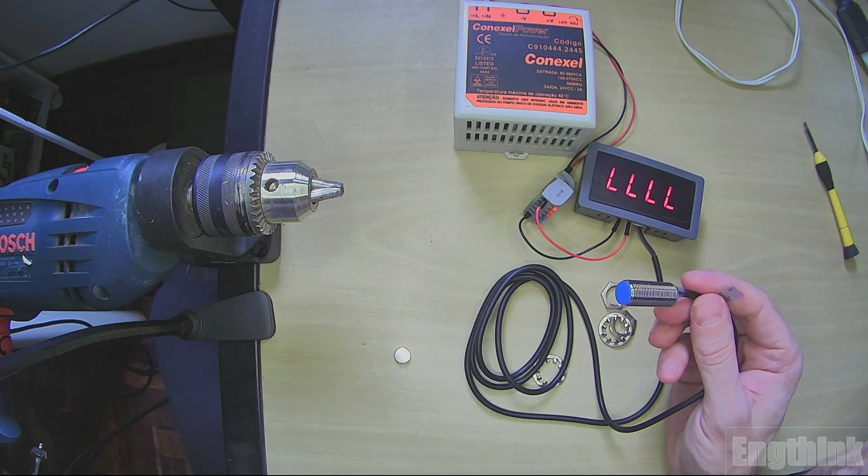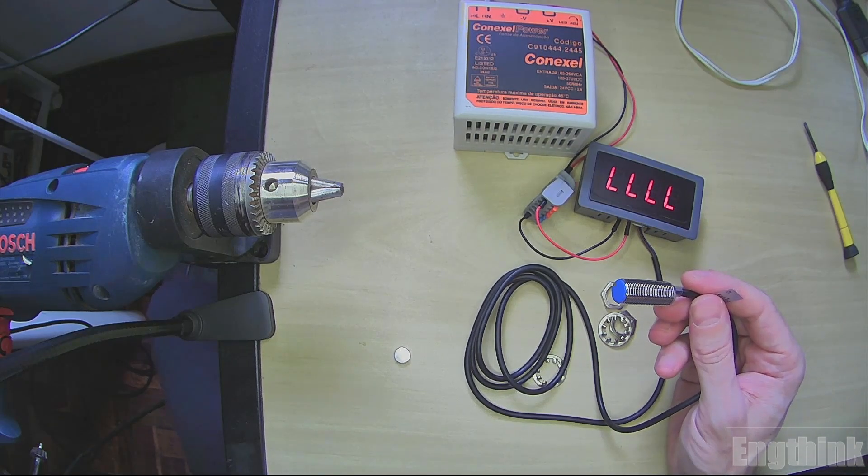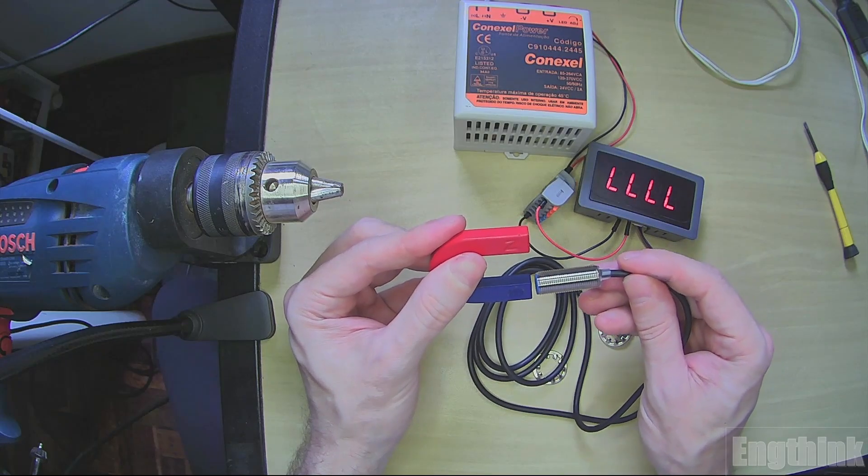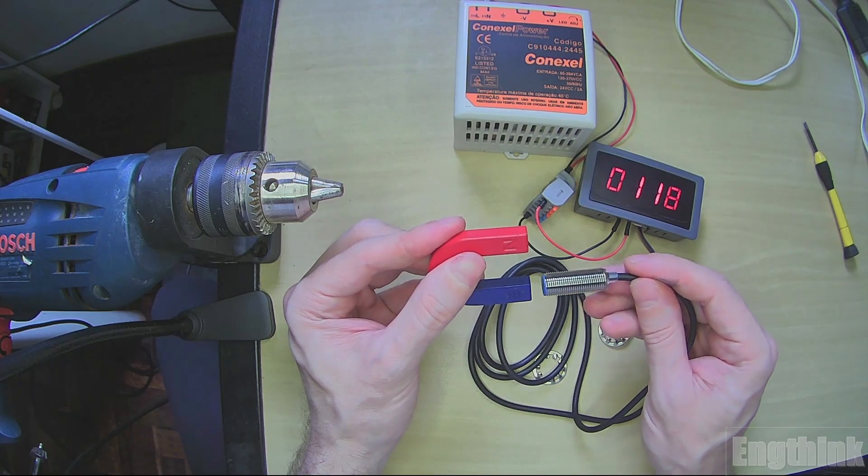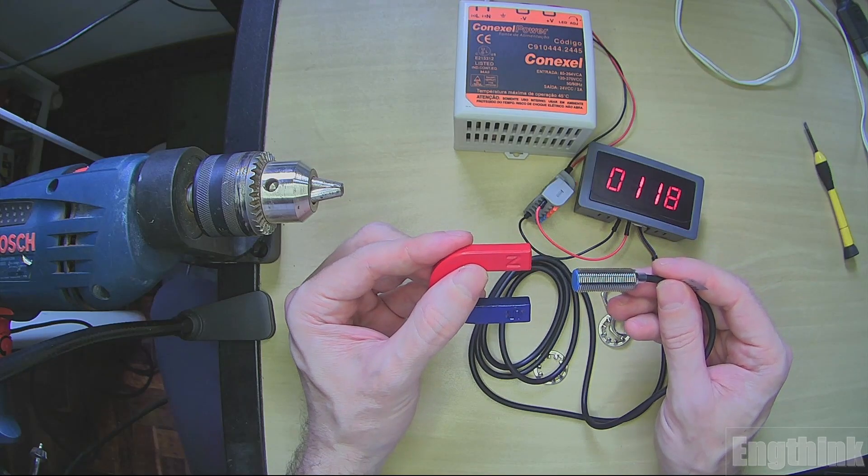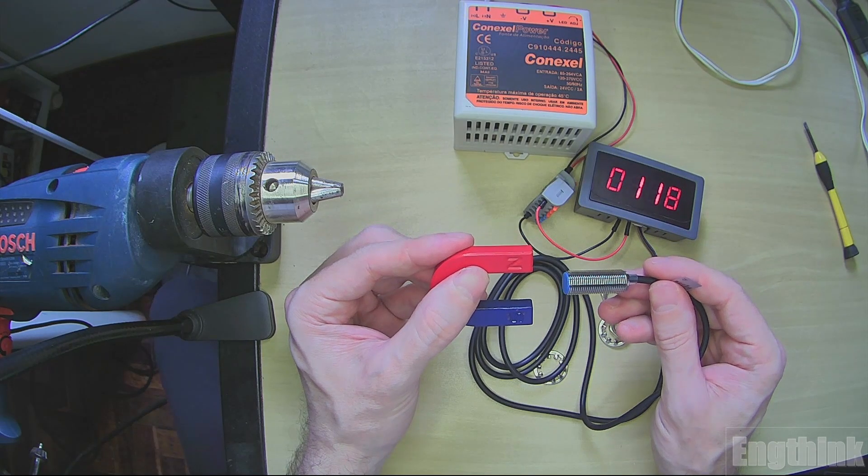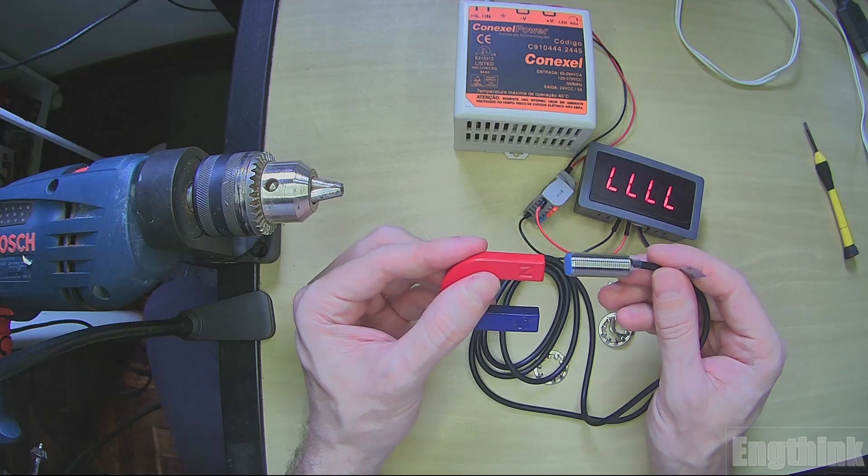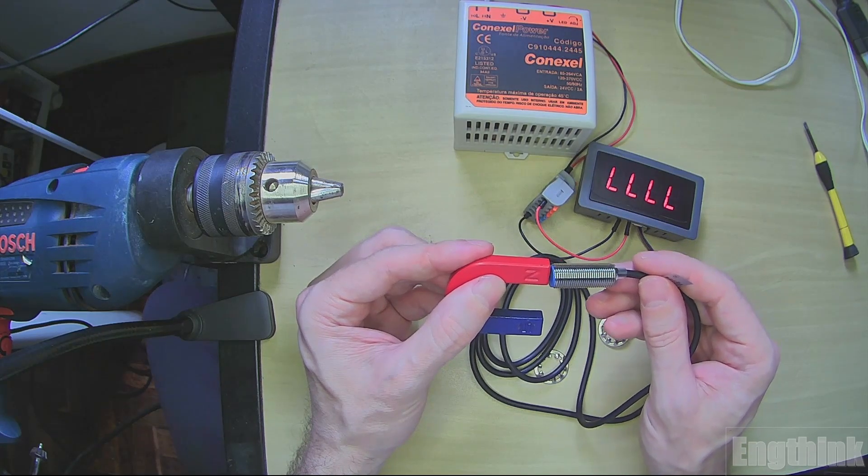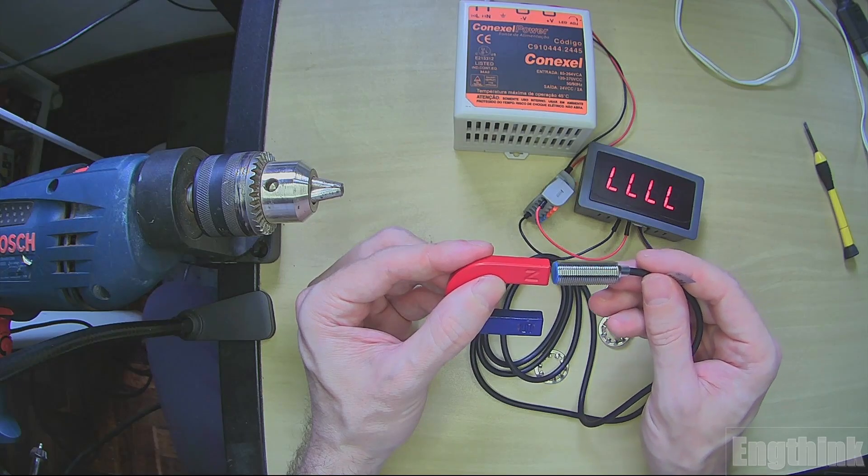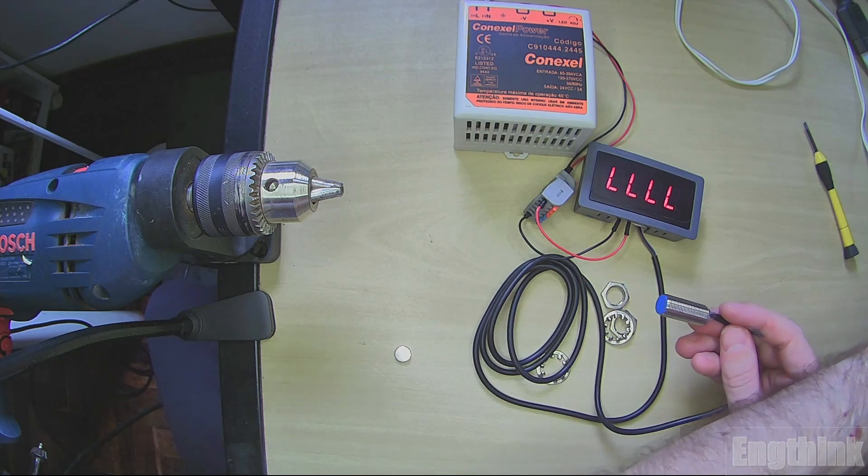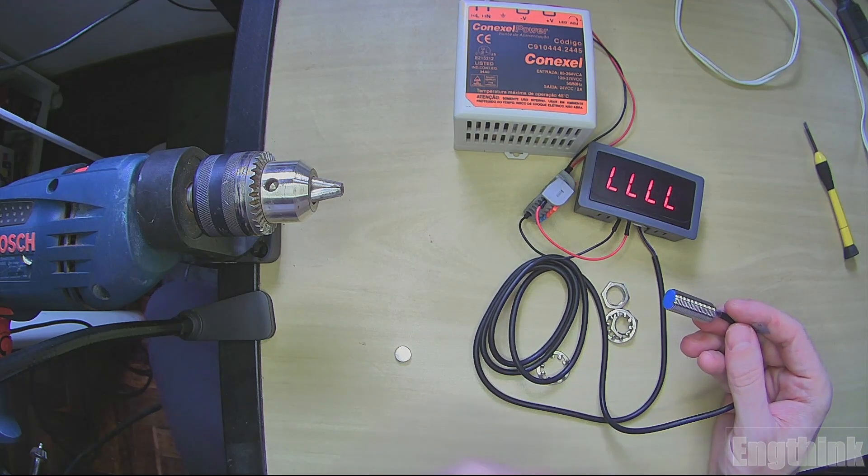Let's check again directly with the magnet with the south pole to confirm. With the south pole we have the indication, but with the north pole we don't have any detection. This is important because if you use the wrong polarity of the magnet we don't have the proper work of the tachometer.